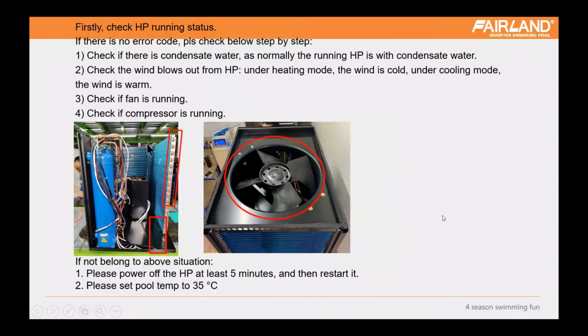So you will go there, check the condensed water, check the vents, check the fan and the compressor running. Sometimes it is stupid, but it's still worth a reminder, because sometimes the customer forgets to set the pool temperature to something different from the local pool temperature. Maybe the water is already 28, but our default setting is 26. So of course the unit will not start. It's not common, but it has happened before.